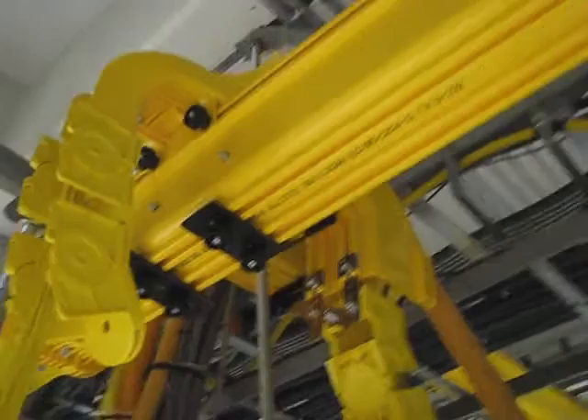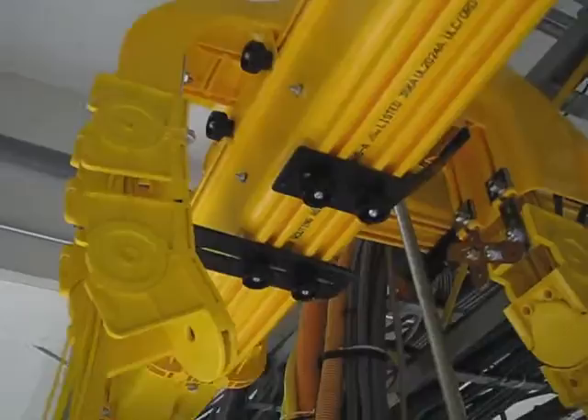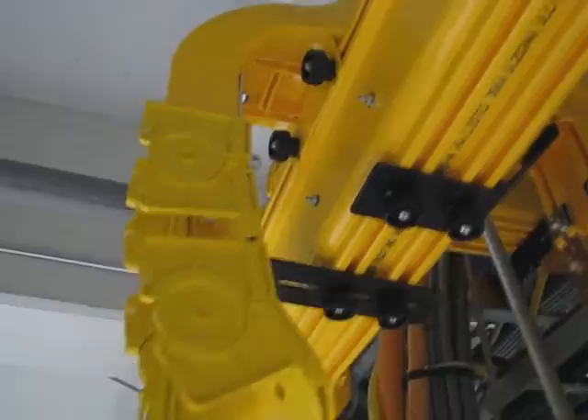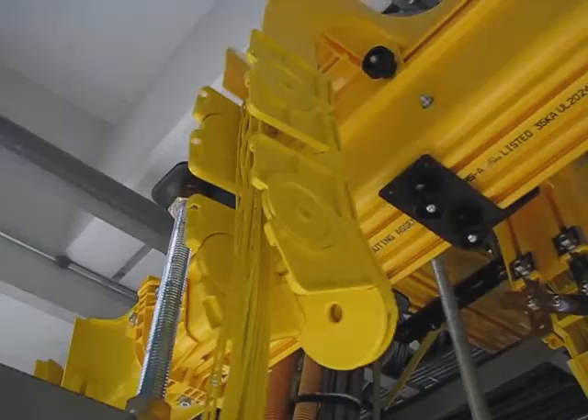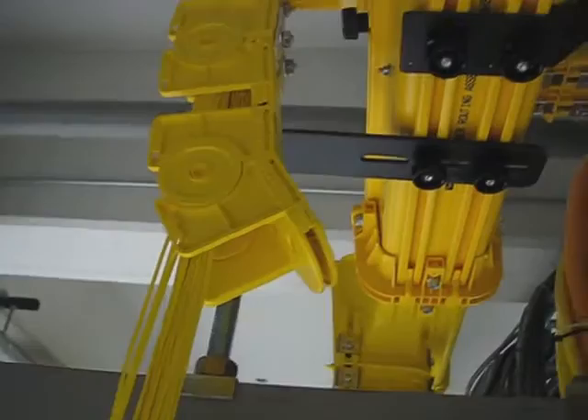Here's my second attempt at running the fiber — I like this better. I've got a four inch express on one side and two inch express on the other. I didn't have a bracket for that so I simply ran bolts directly into the trough. One of the nice things about these sectional telec troughs is that I can put them in piece by piece. You can see a little impromptu bracketry there.